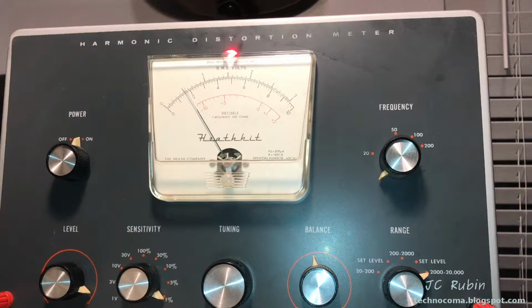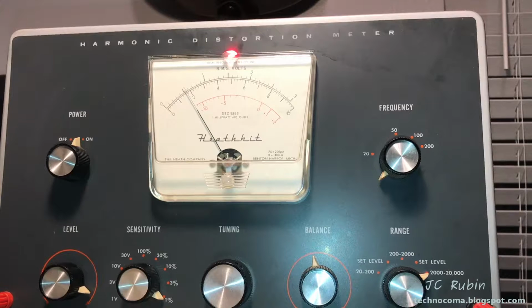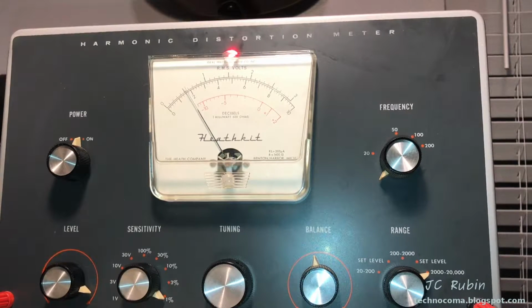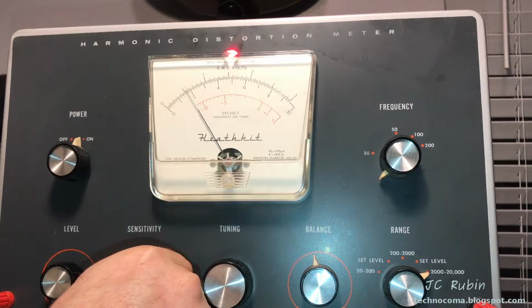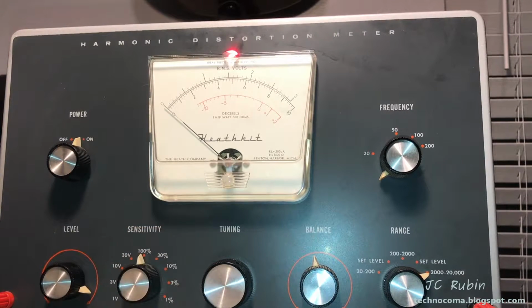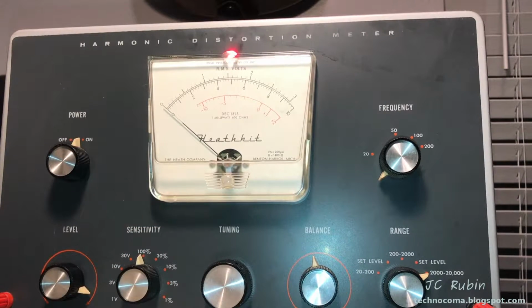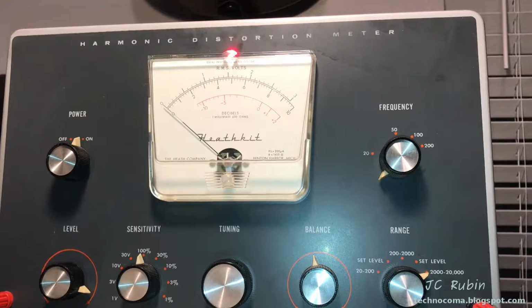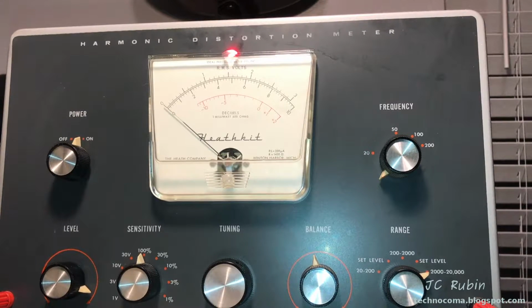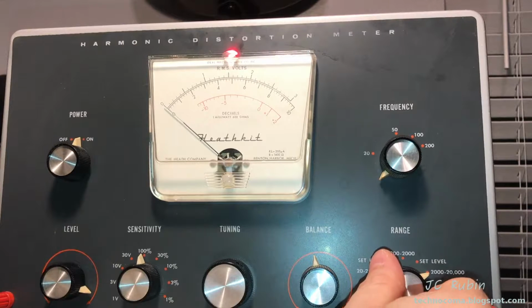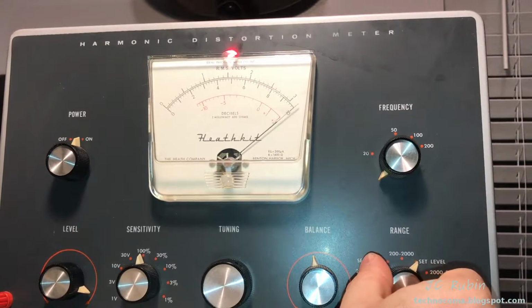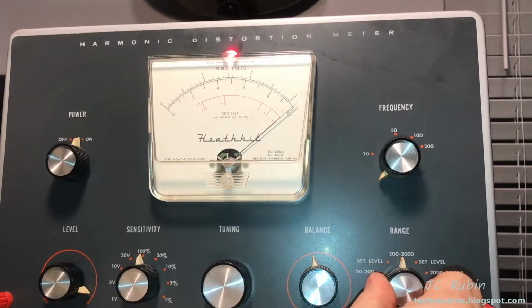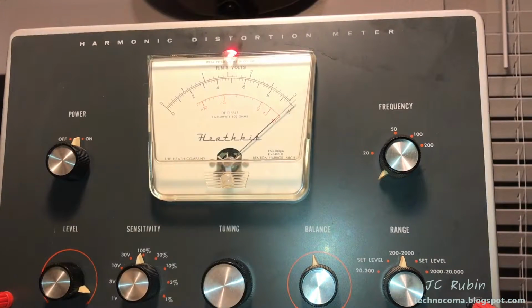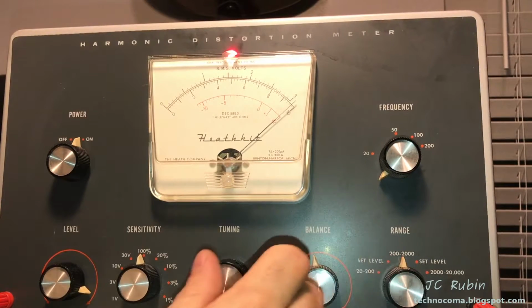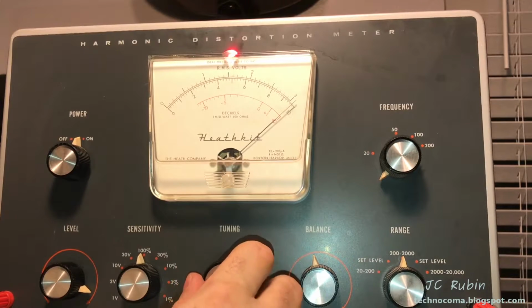This is not the end of the balance adjustment. This is only halfway through. So now it says with the sensitivity switch now at 100%, so turn it back to 100. Right, there we go. Turn the tuning control for a minimum meter indication after setting this to the 200, 2000. So set level is where we left it before, right? Now we're 200, 2000. And we're going to have to tune this now for a minimum indication.